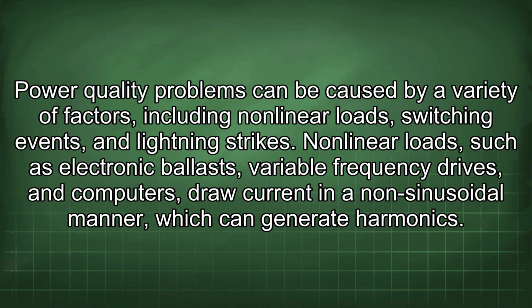Power quality problems can be caused by a variety of factors, including nonlinear loads, switching events, and lightning strikes. Nonlinear loads, such as electronic ballasts, variable frequency drives, and computers, draw current in a non-sinusoidal manner, which can generate harmonics.